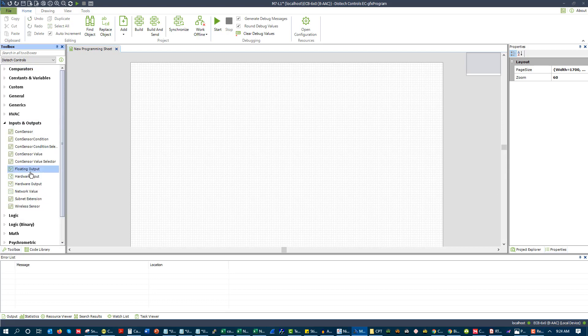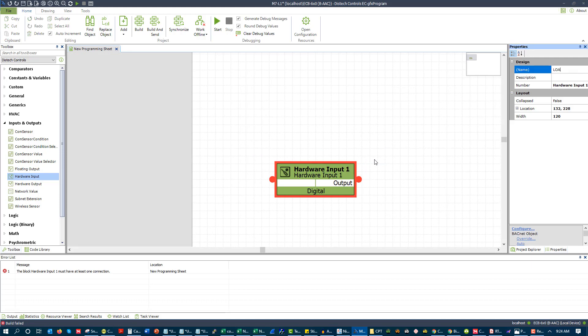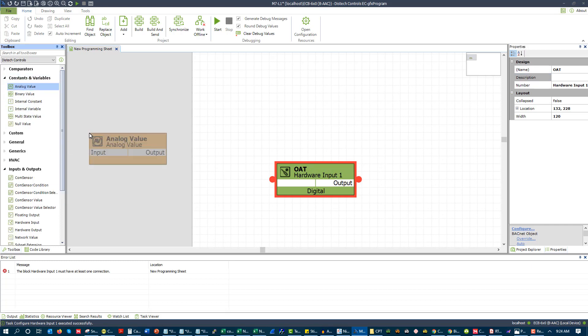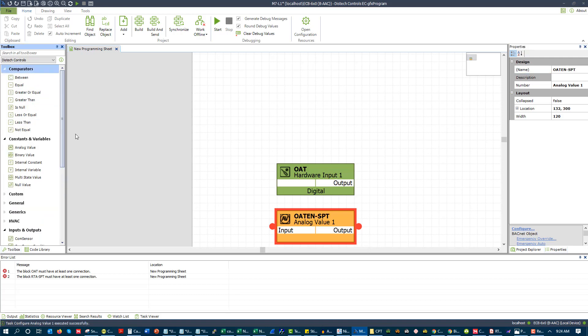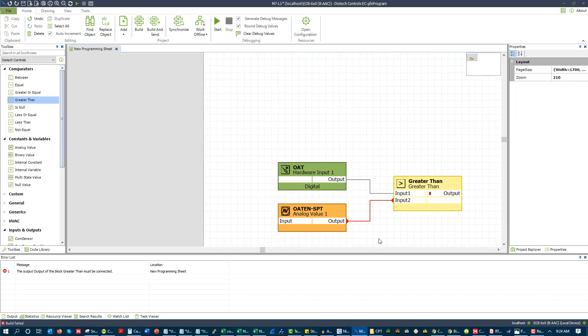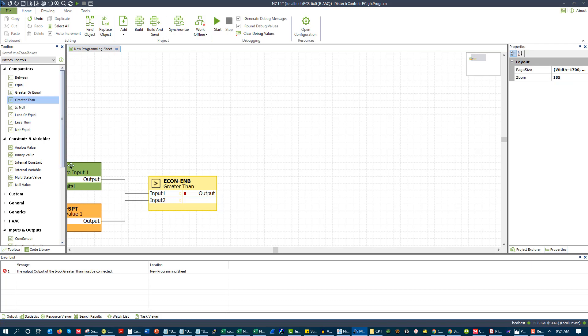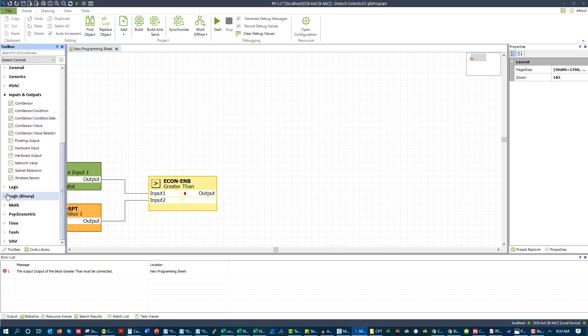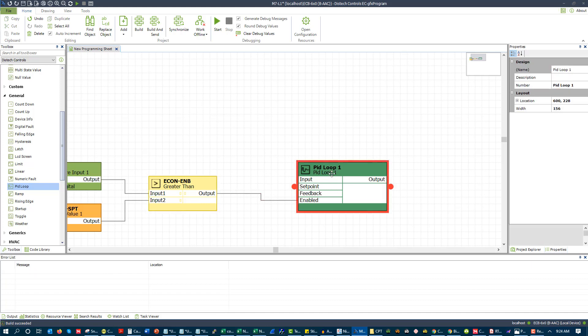So let's say that I'm told — let's zoom in here — when outdoor air temp is greater than the outdoor air enable set point, then I'm going to go and turn on my economizer. So if outdoor air temp is greater than outdoor enable set point, I'm going to have — we could just call this econ enable — that is going to give me an output which is going to drive my economizer being enabled.